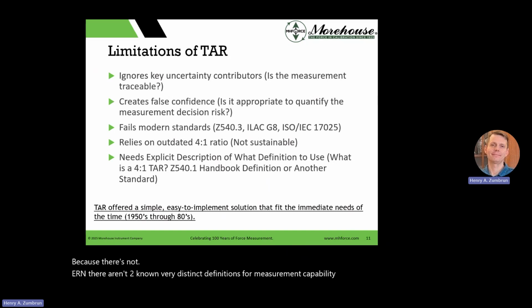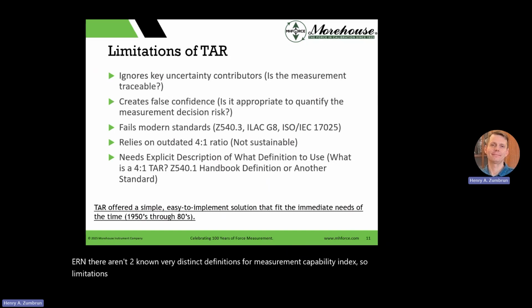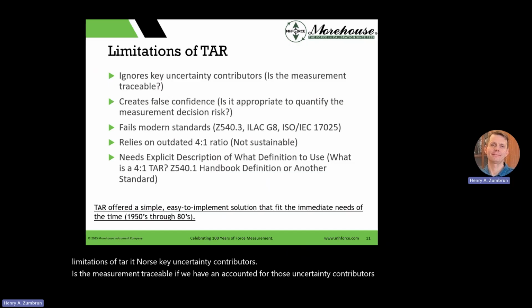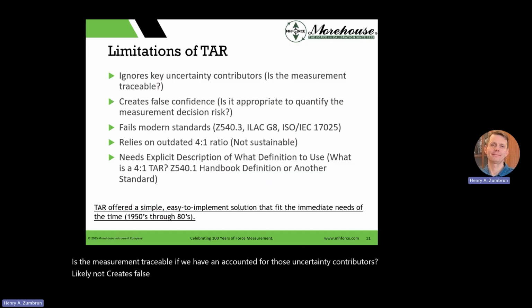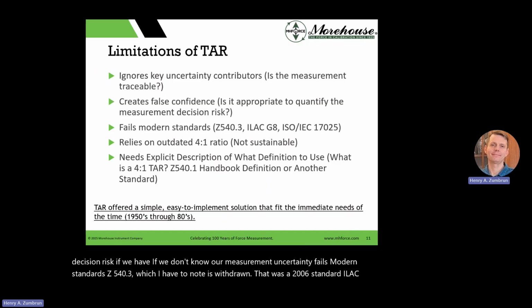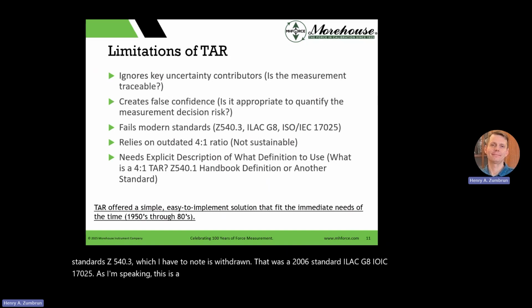So limitations of TAR. Ignores key uncertainty contributors. Is the measurement traceable if we haven't accounted for those uncertainty contributors? Likely not. Creates false confidence. Is it appropriate to quantify the measurement decision risk if we don't know our measurement uncertainty? Fails modern standards: Z540.3, which I have to note is withdrawn. That was a 2006 standard. ILAC G8, ISO IEC 17025. As I'm speaking, this is a 2017 version. ILAC G8 is a 2019 version.